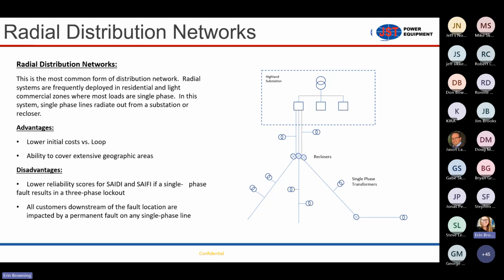Our breaker can interrupt just one phase, right? So if you have a tree branch hitting one phase, the other two phases are going to be fully energized. They're not going to see any flashing lights, any on off of the lights. Only one phase is going to see that.